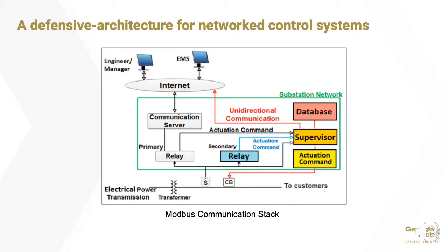Each controller sends actuation commands to the isolated supervisor device. The supervisor examines both commands to determine if either is erroneous by comparing the commands to a database of known sensor values and corresponding actuation commands. If an abnormal output signal is provided by the network controller, the supervisor switches to the isolated secondary controller and sends a unidirectional alert message via the Internet through a specified open port to alert the remote management system that a potential cyber attack is present.